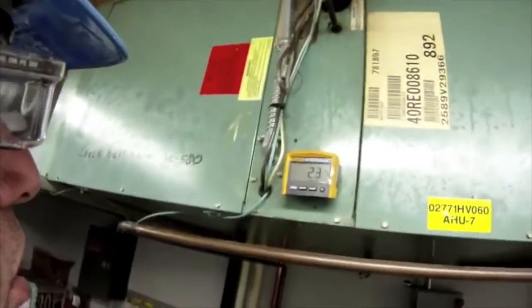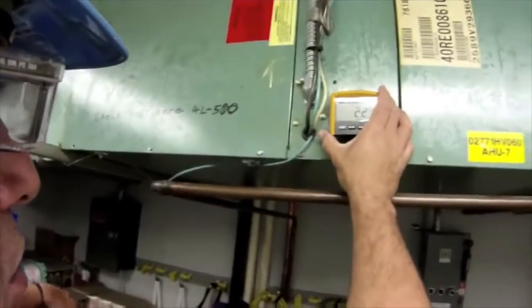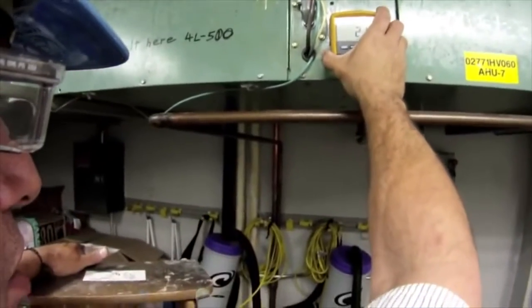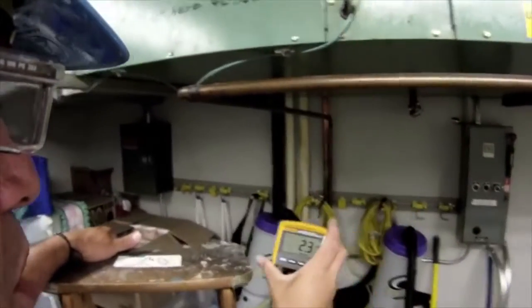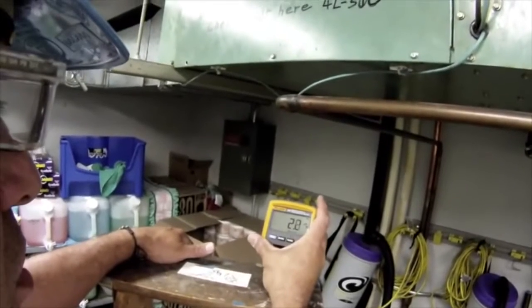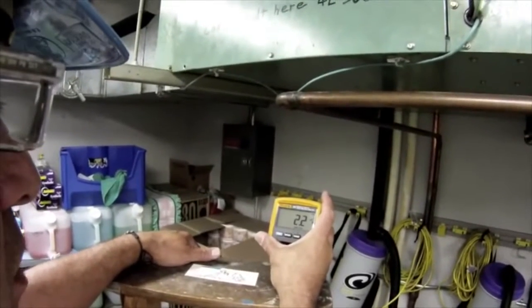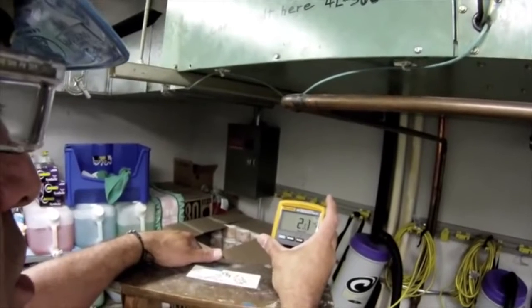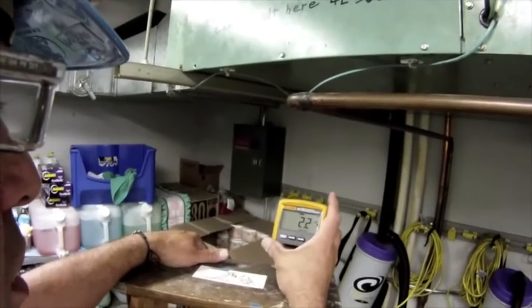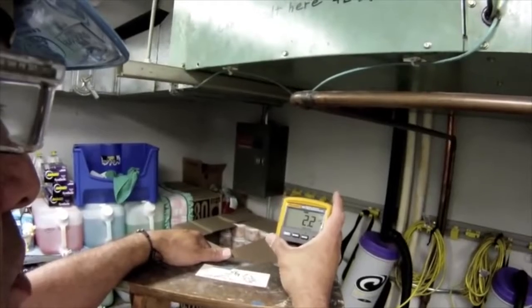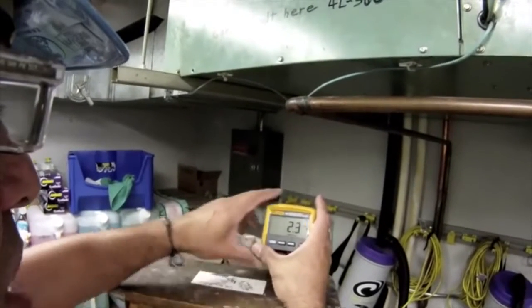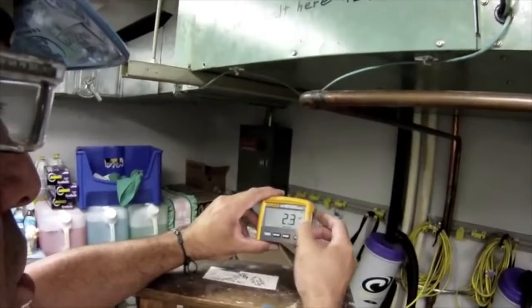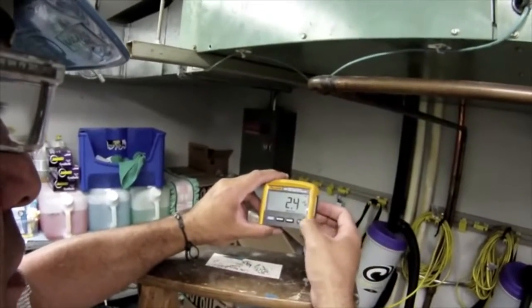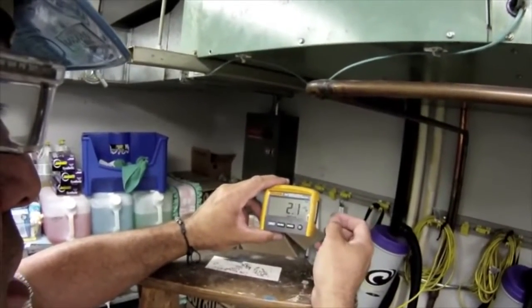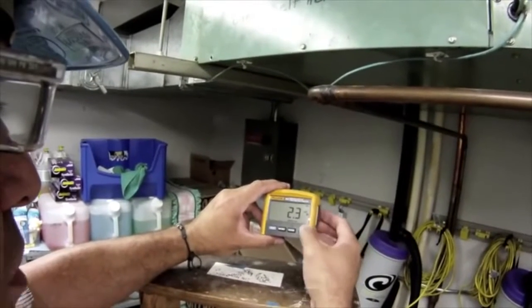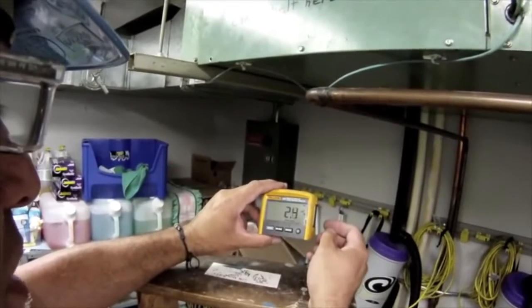I expect to see less than 3.2 amps on this motor. Right now, with the fan on a load, I'm drawing 2.1 amps, 2.2. I can press hold and it will capture the highest amp reading. If I'm in a dark environment, I can also turn on a backlight. I don't know if that shows up very well in the video, but if I'm in a dimly lit room, there's backlighting, and I'm pretty satisfied with my motor.